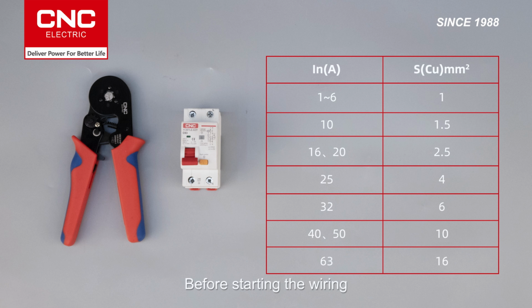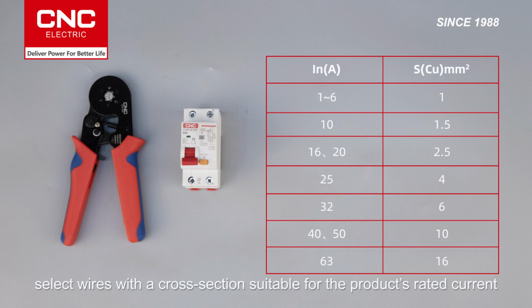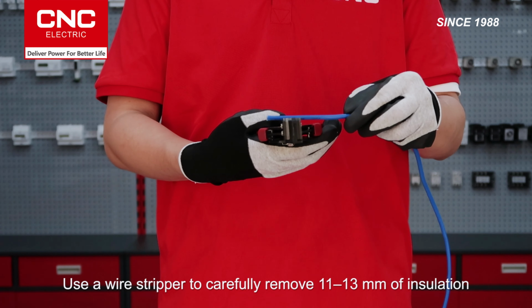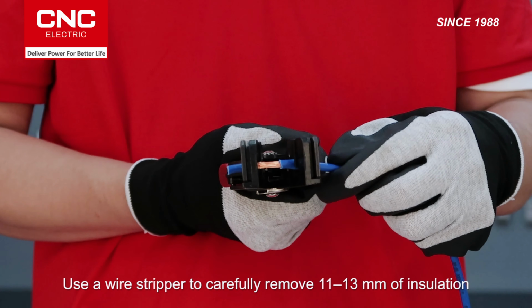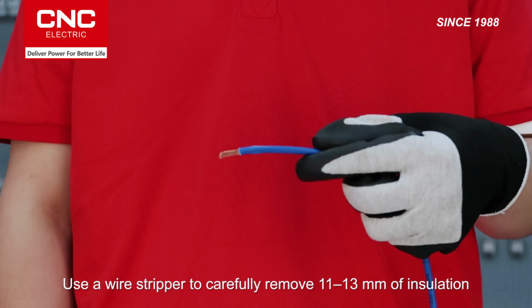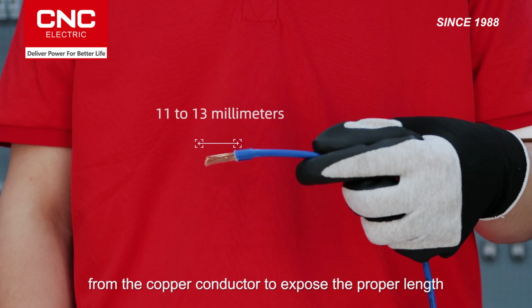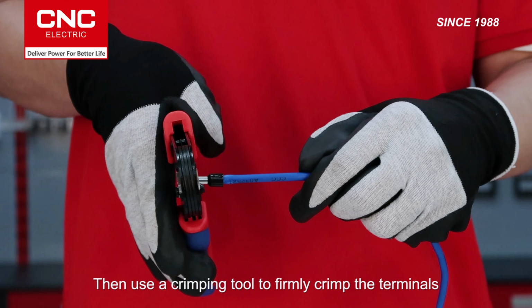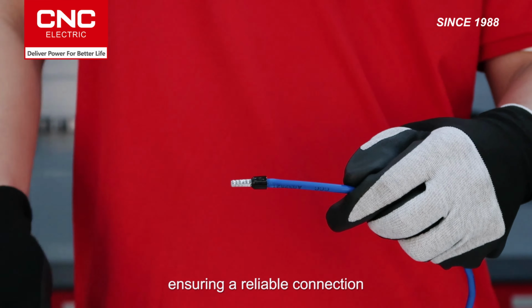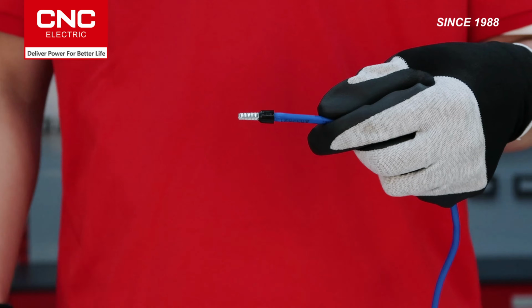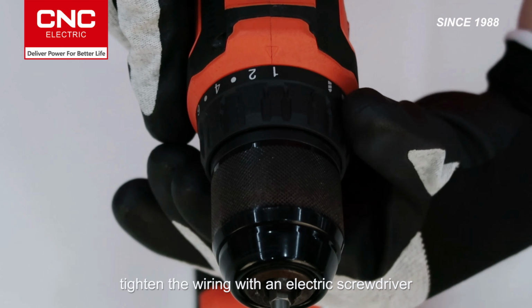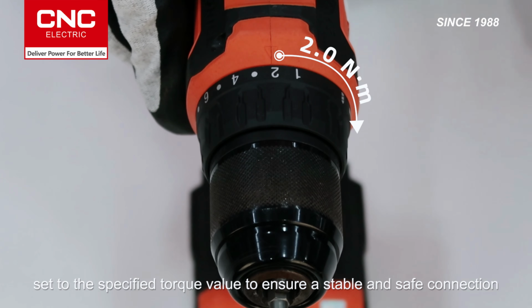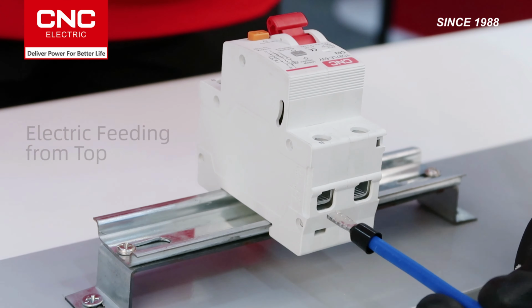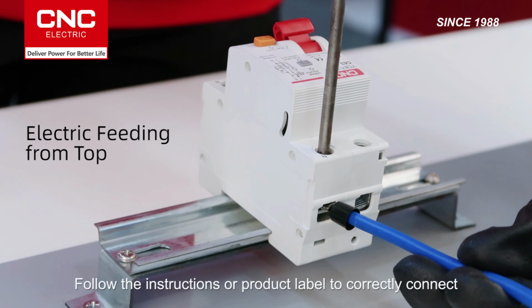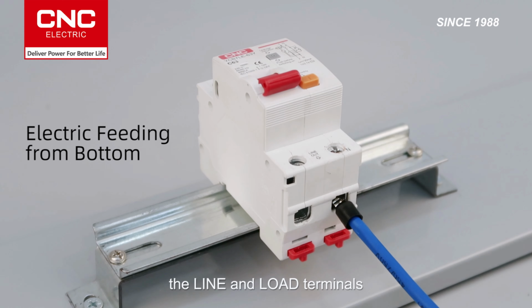Before starting the wiring, select wires with a cross-section suitable for the product's rated current. Use a wire stripper to carefully remove 11-13 mm of insulation from the copper conductor to expose the proper length. Then use a crimping tool to firmly crimp the terminals, ensuring a reliable connection. Finally, tighten the wiring with an electric screwdriver, set to the specified torque value to ensure a stable and safe connection. Follow the instructions or product label to correctly connect the line and load terminals.